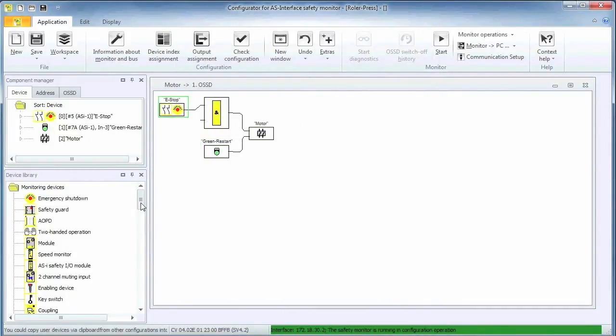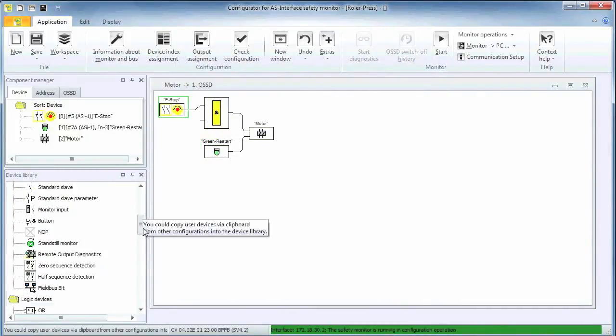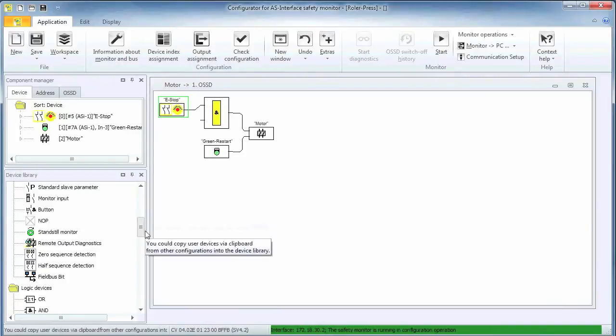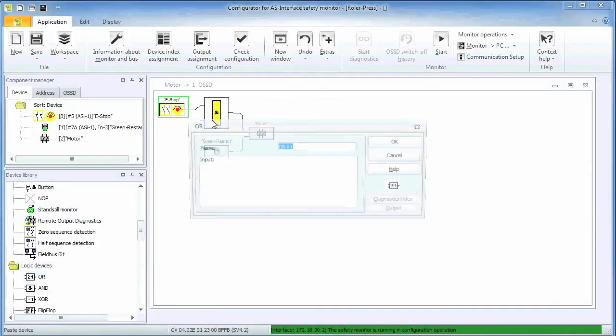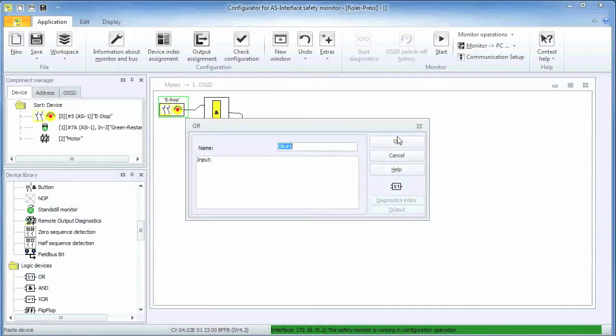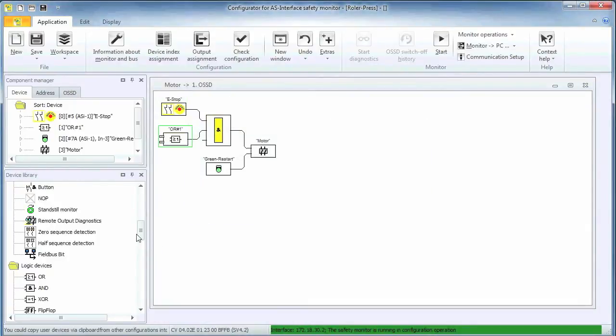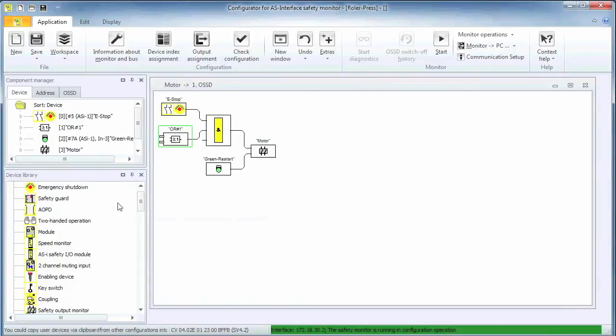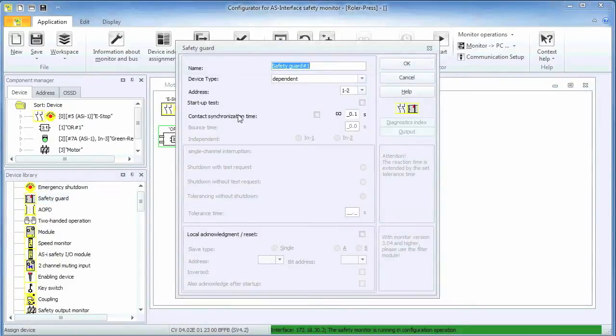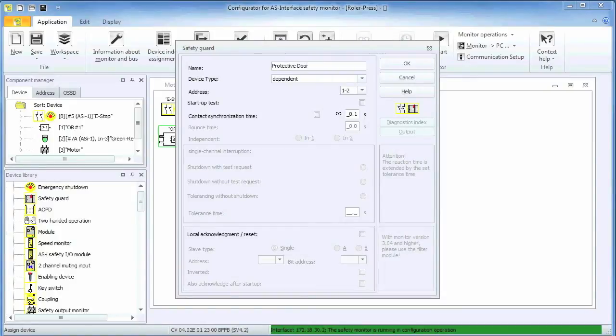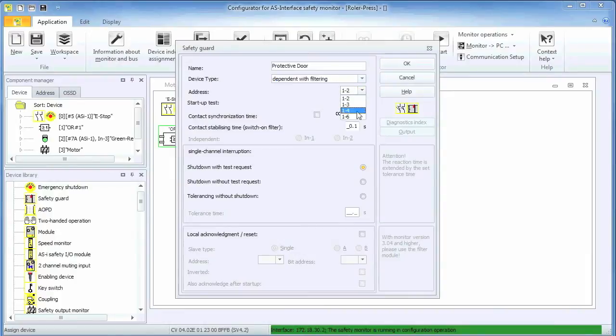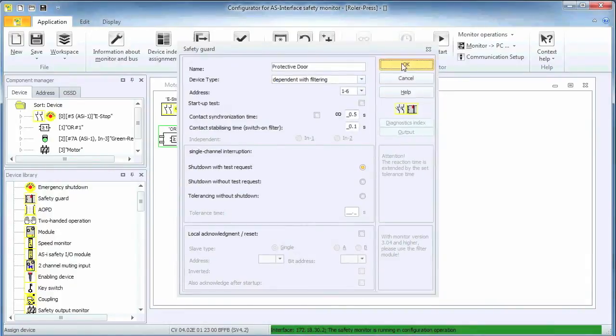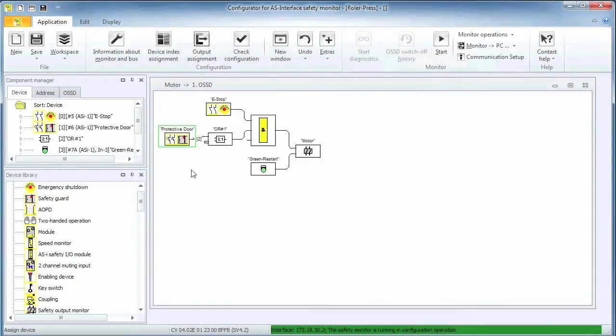The OR function block is used to set up the logic that deals with the safety encoder signals and the protective door. Just recall that the output of the OR is true as long as at least one of its connected inputs is true. Adding the protective door function means that as long as the door is closed, the OR will be true. No matter the state of any other function block, we will be adding to this OR block later.